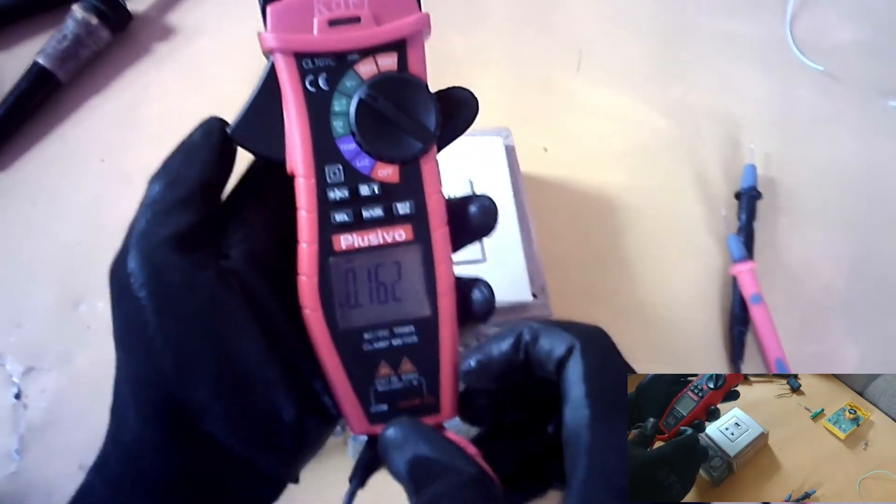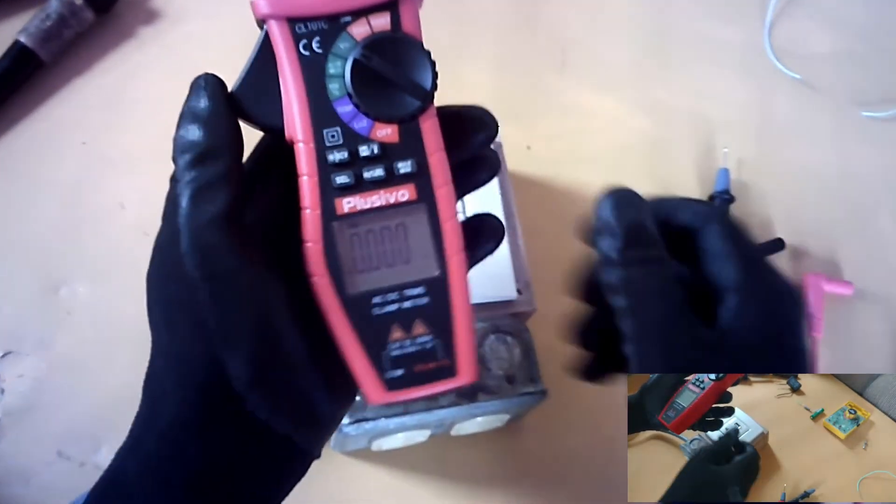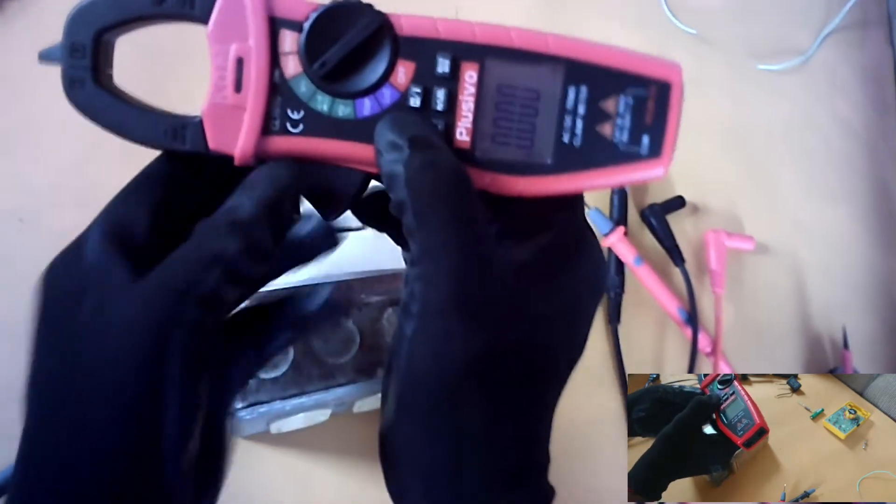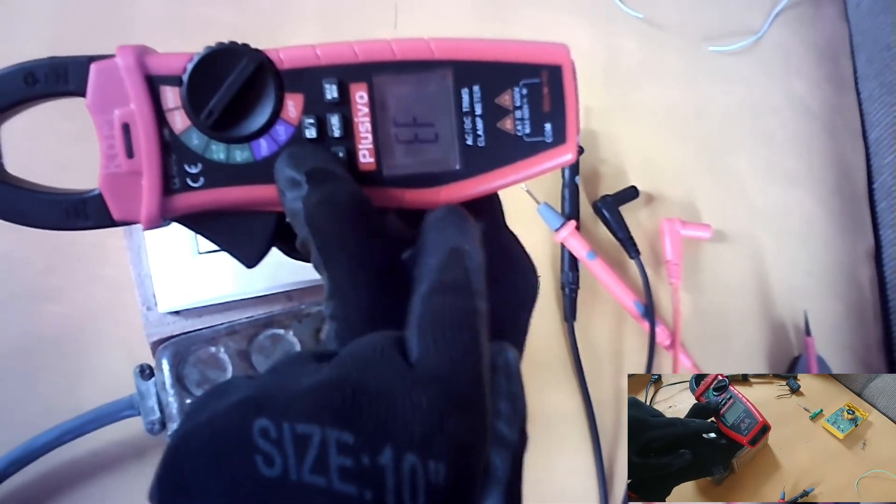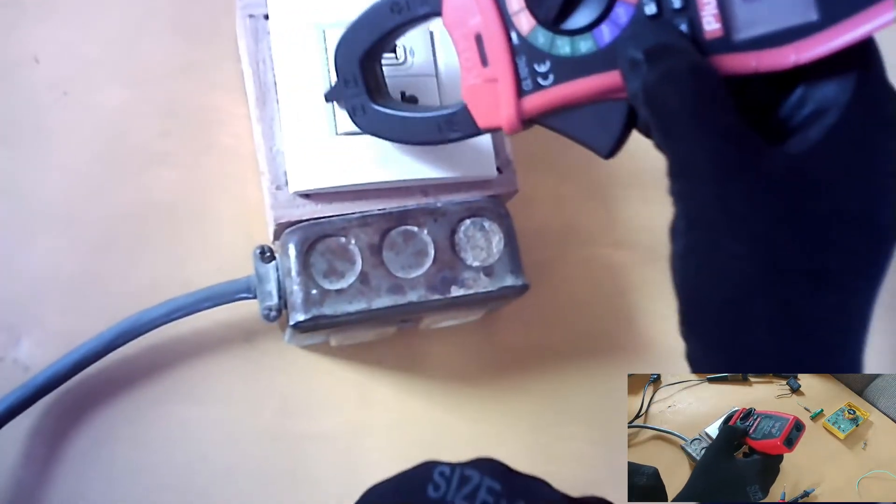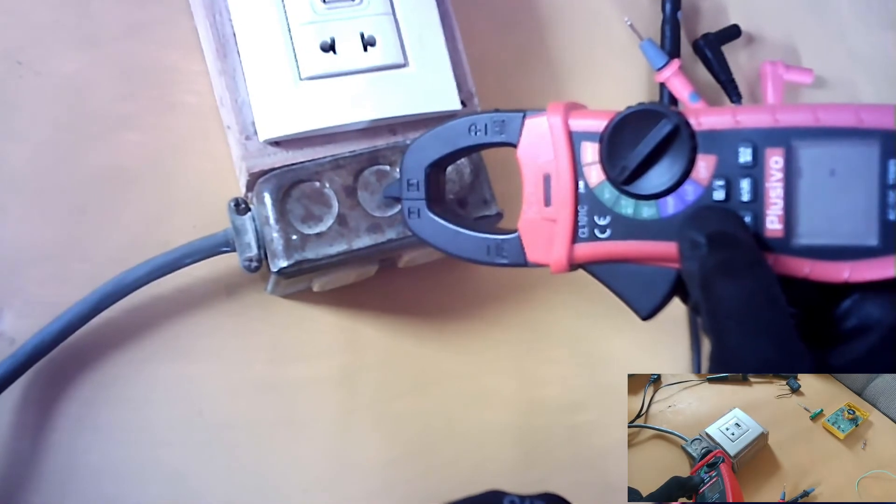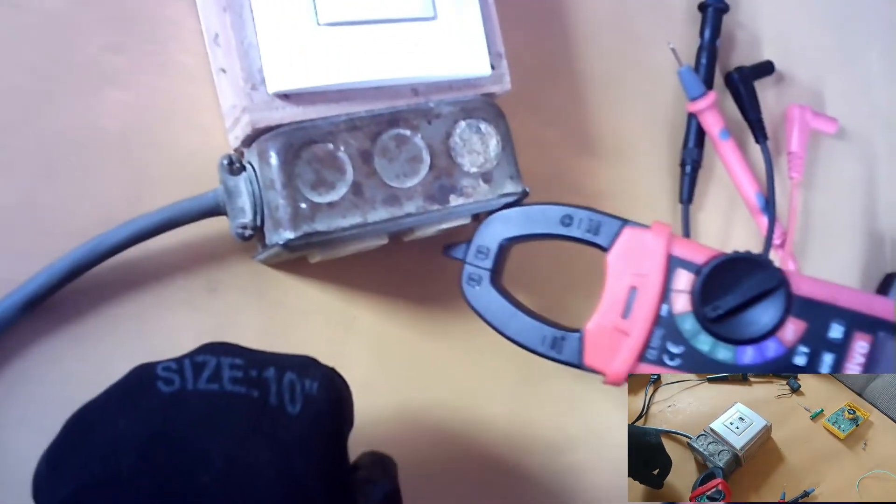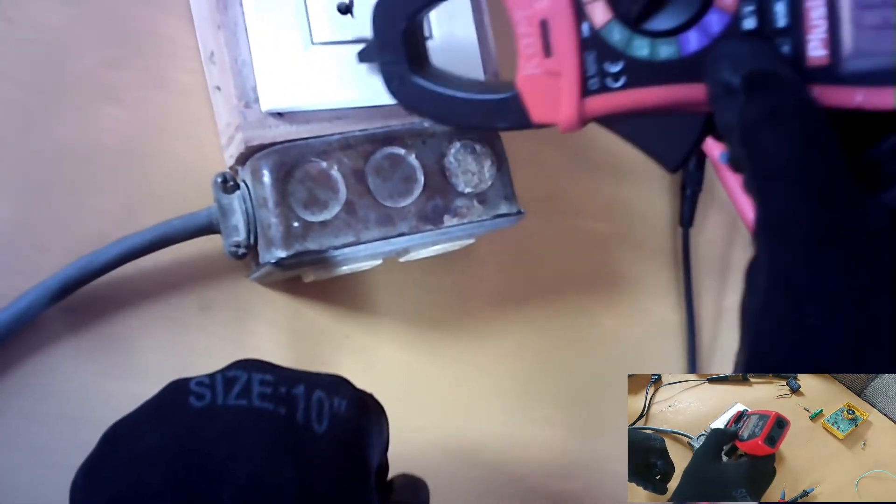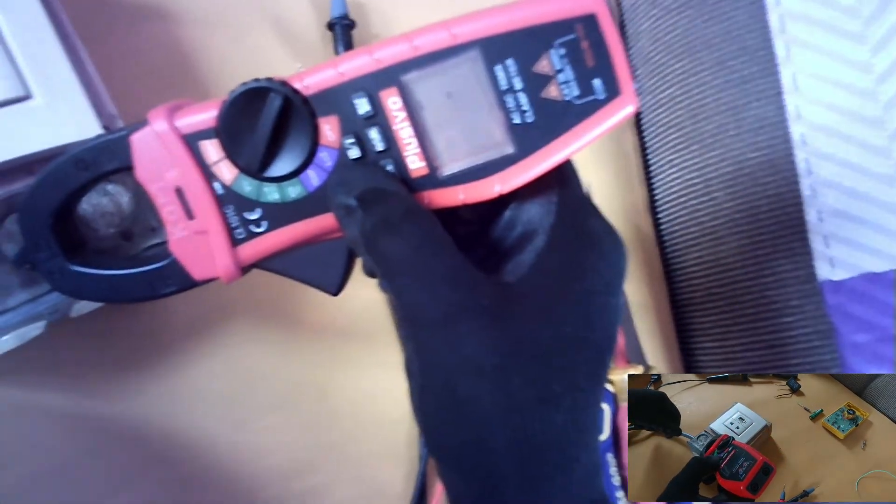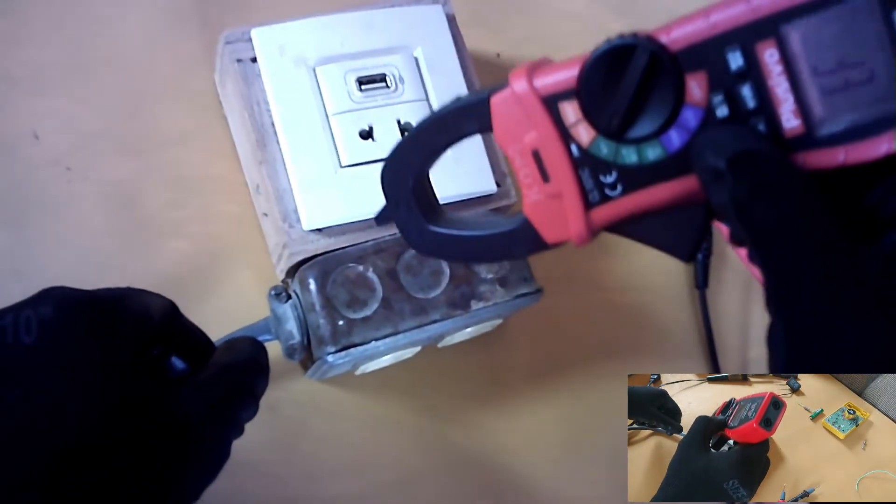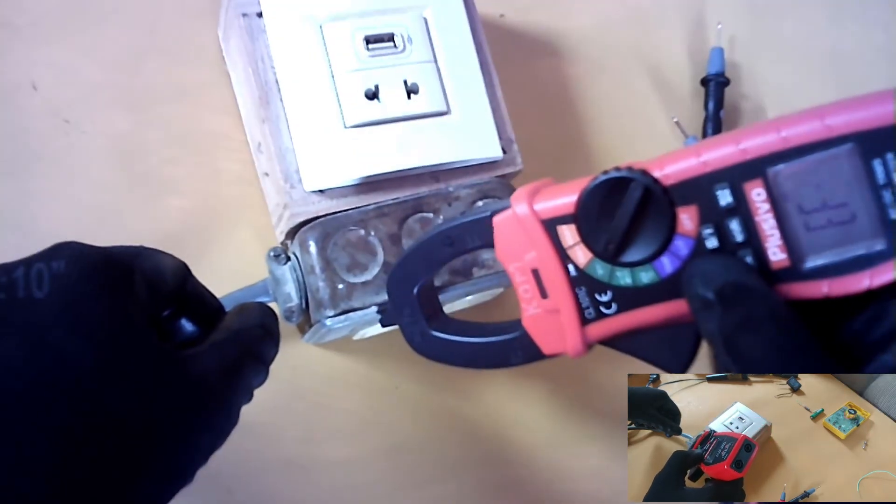And I also have an NCV feature. That's for non-contact volt check. Press and hold this button. EF comes on the display. And you just bring it, this is the sensor, and you just bring it across where you expect the voltage should be. AC, and this only works for AC volts. And the closer it is, the faster it beeps.